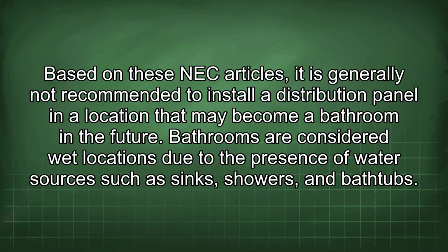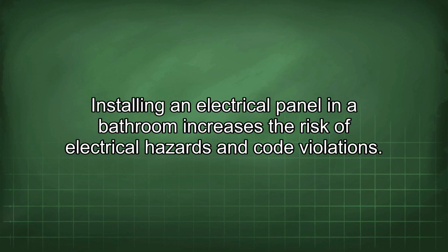Based on these NEC articles, it is generally not recommended to install a distribution panel in a location that may become a bathroom in the future. Bathrooms are considered wet locations due to the presence of water sources such as sinks, showers, and bathtubs. Installing an electrical panel in a bathroom increases the risk of electrical hazards and code violations.